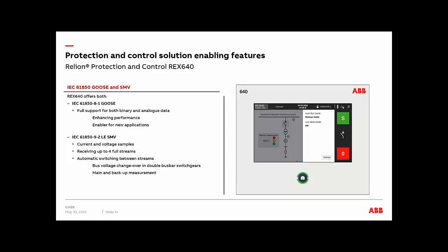Here on the right side, you can see a view of the HMI, and pretty much, I don't think we show it on the screen here, but the way this will work, you will have a single line diagram, and if you want to operate or see anything regarding that specific element, you will just touch it, and the relay will pop up, either close or open. If it's a synchronizer, you can start, like in this case, manual mode or automatic mode. It will give you information on each of the elements, and everything is going to be based on your single line diagram there.